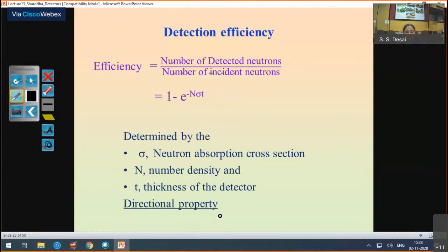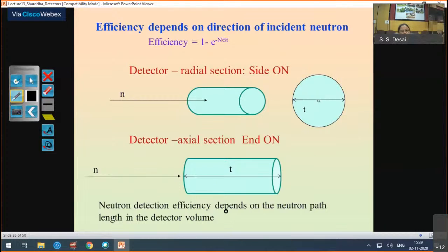As we have seen for sensitivity, for each detector, sensitivity and efficiency are very different, and both are important. They are considered depending on the way we are going to use the detector. If it is used for area monitoring, yes, sensitivity is important. But for neutron scattering applications, when we have a neutron beam with neutrons coming from a particular direction, efficiency is more of a consideration.